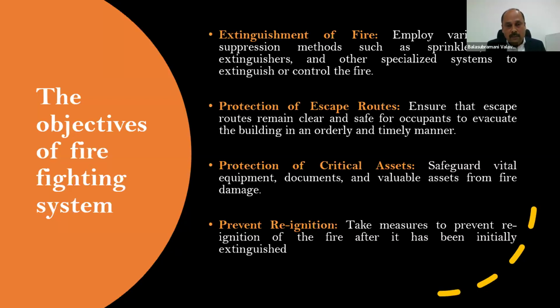In some cases, what happens when you put out the fire manually, there may be smoke which will reinitiate the fire. So when you have this particular system in place, for example a fire suppression system or firefighting system, at the initial stage itself it will be extinguished.